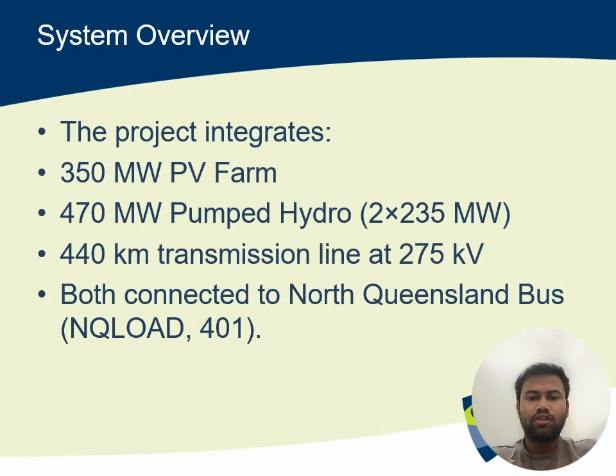Now let's look at the system components that make this project a reality. The core of the integration includes a 350 megawatt PV solar farm and a substantial 470 megawatt pumped hydro facility, which is a combination of two units of 235 megawatt each. To connect this powerful generation to the grid, we are building a 440-kilometer long, 275 kilovolt transmission line. All of this will ultimately connect to a North Queensland bus, or NQ load, in our Australian national grid.